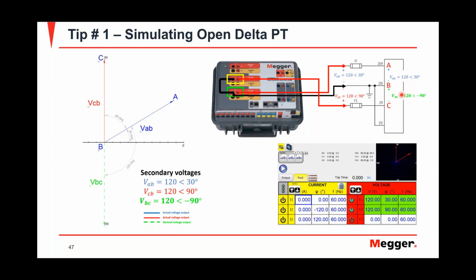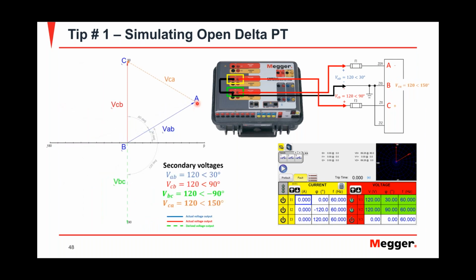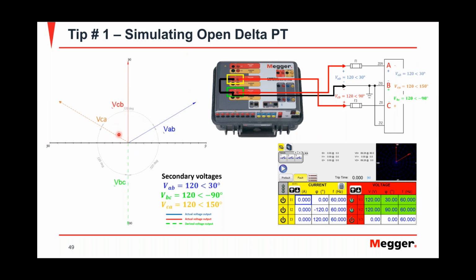It's going to see the voltage from B, your polarity on B, to C. So this voltage is derived. You inject C to B voltage, but you derive B to C. This is what the relay is going to see. So using 2 voltage channels, you get a 3-phase voltage. The last voltage is also going to be derived, which is the voltage from C to A. That's this voltage right here, and on a phasor diagram it will look like that. So when you move it together, you move this to the origin, and that's your 3-phase voltages on your expected values into the relay. So this is how you would do an open delta connection for a relay.